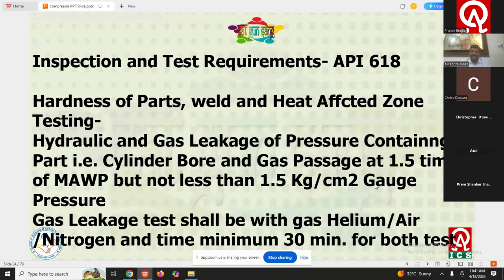This is a condition given additionally, for when my compressor is working at a very low pressure, say 0.5. So as per this condition, the testing pressure must be 1.5 times 0.5, so the testing pressure may be 0.75. But for that case, the condition is given that if the pressure is so low, at least the hydraulic testing shall be at 1.5 kg per centimeter square.